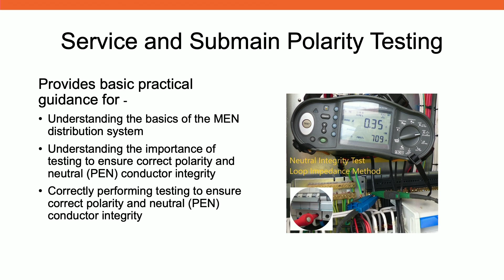We've got another one on service and submain polarity testing. One of the big issues with service and submain testing is that people underestimate the importance of the PEN conductor. The protective earth neutral conductor, as in the supply conductor prior to the MEN system, is an earth conductor as well as a neutral conductor. It is critical. It is the most critical earth conductor in an installation.